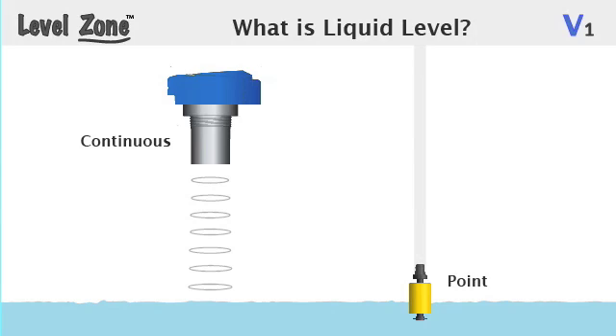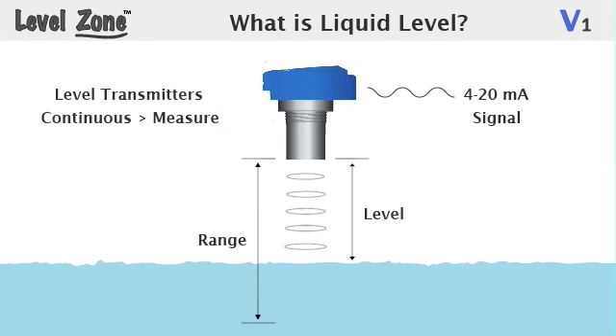There are two basic types of liquid level sensors: continuous and point. Continuous sensors measure level within a specified range and provide a 4-20 milliamp signal output that is proportional to the measured level. These sensors are called level transmitters and are typically used for inventory and process monitoring.